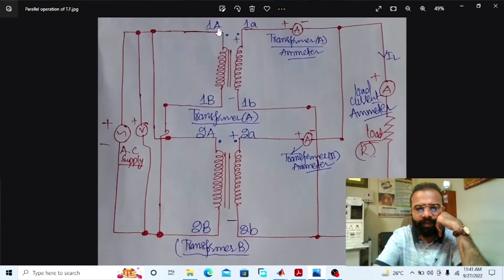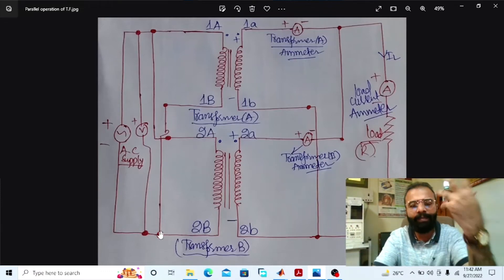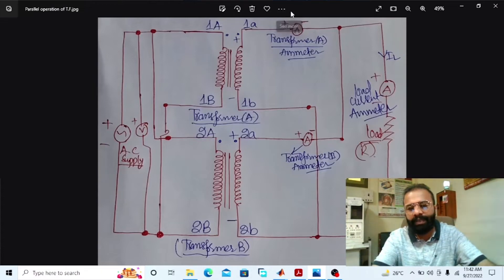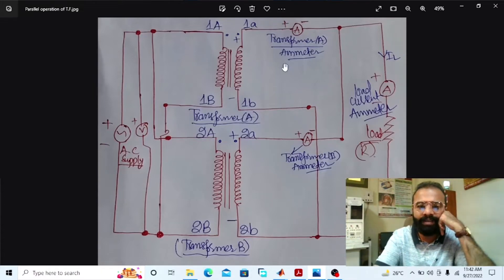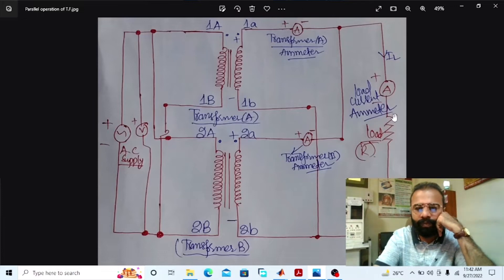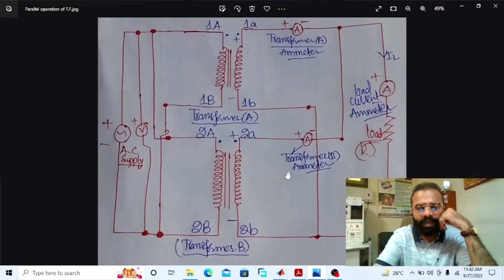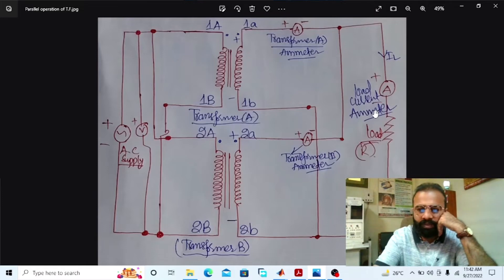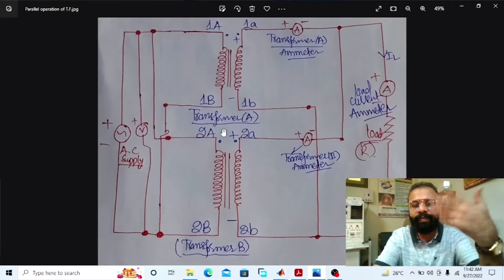The A terminals of both transformer primary sides are connected to each other, and the B terminals of both transformer primary sides are connected to each other. The ammeter connected in series with transformer A gives us the current shared by transformer A to the load busbar, and the ammeter connected in series with transformer B gives us the current shared by transformer B to the load busbar. Another ammeter gives us the total load current flowing from the load side.